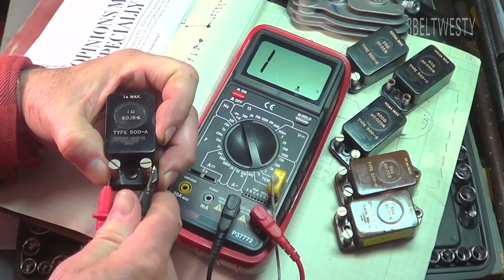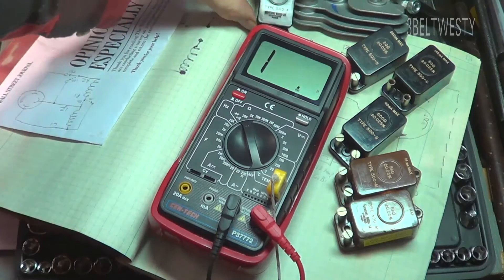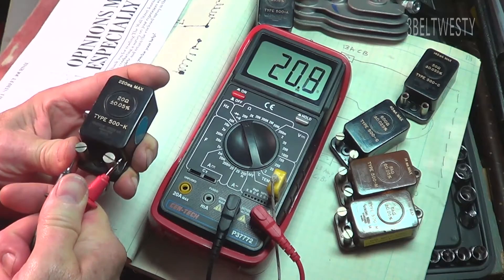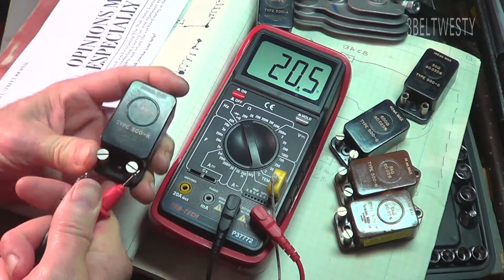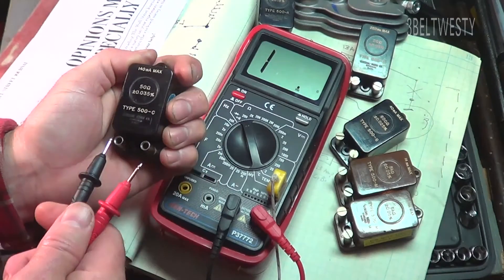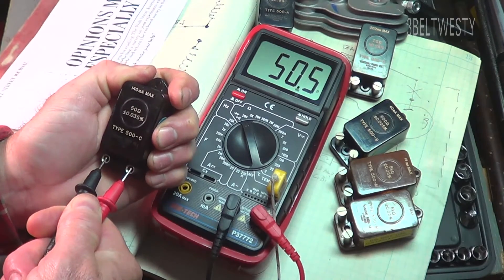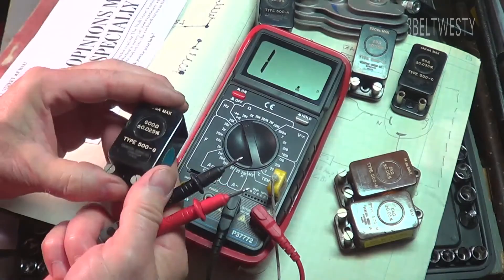Take up the 1 ohm standard — there it is. 1.6, so that one's on the money. Here's a 20 ohm gizmo and 20.8, so it's on the money there. Here's a 50 ohm General Radio standard — 50.5, pretty close. Here's a 600 ohm.